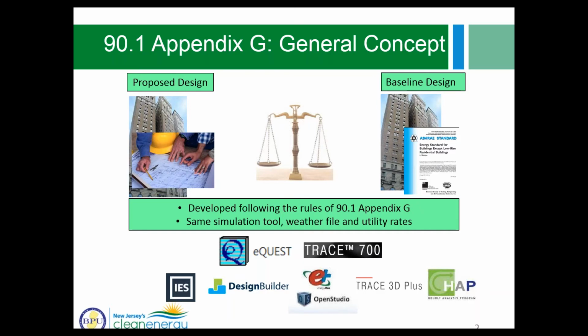But both models, the proposed design model and baseline model, must be developed following the rules of 90.1 Appendix G, using the same simulation tool, weather file and utility rates. There are a number of simulation tools that meet requirements of Appendix G. In P4P, the overwhelming majority of models that we see are developed using either eQuest or TRACE. But there are other tools that could be used. We do ask that if you use any tool other than eQuest or TRACE, you reach out to the program beforehand so that we have an agreement on simulation reports that would need to be submitted, and so that we could reaffirm that the tool that you are considering in fact complies with 90.1 and is allowed in the program.